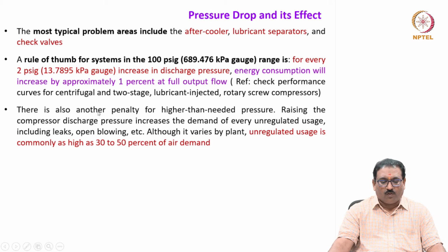There is also another penalty for higher than needed pressure. Raising the compressor discharge pressure increases the demand of every unregulated usage, including leaks, open blowing, etc.